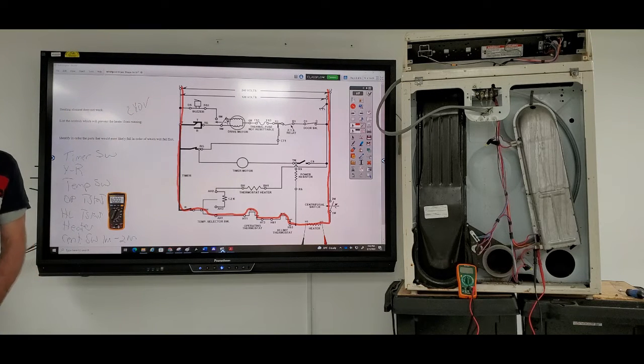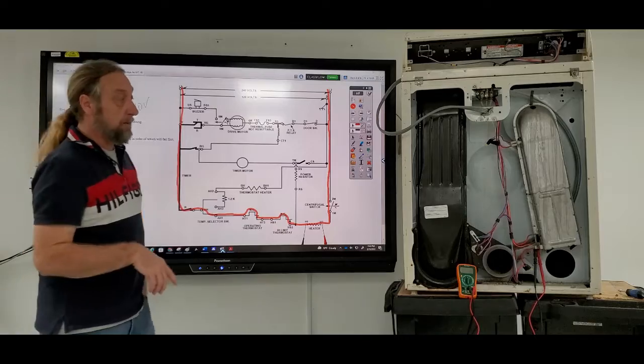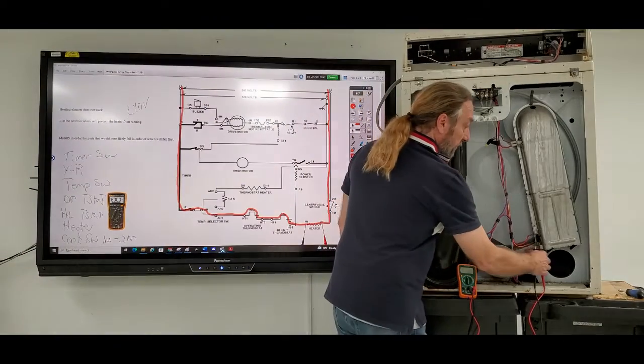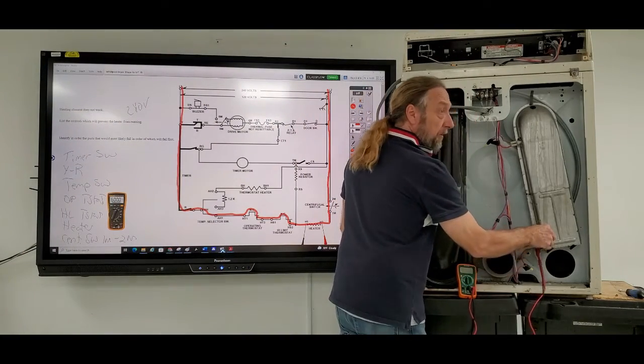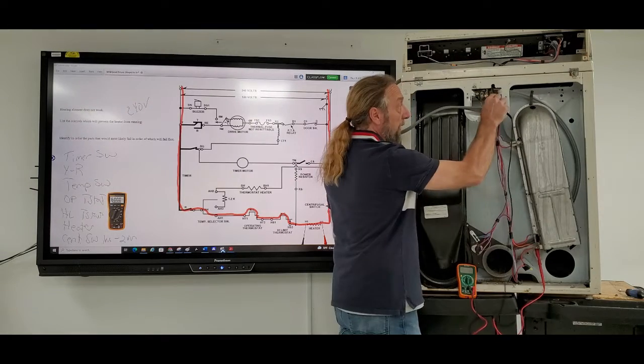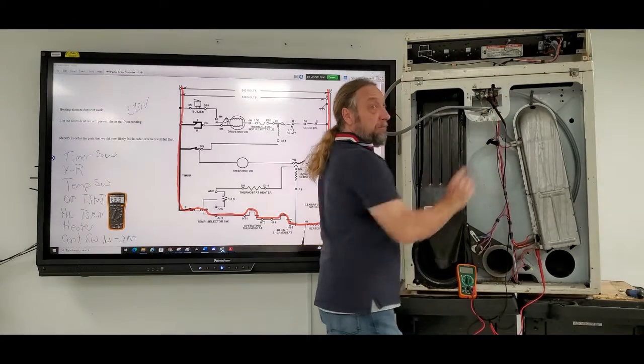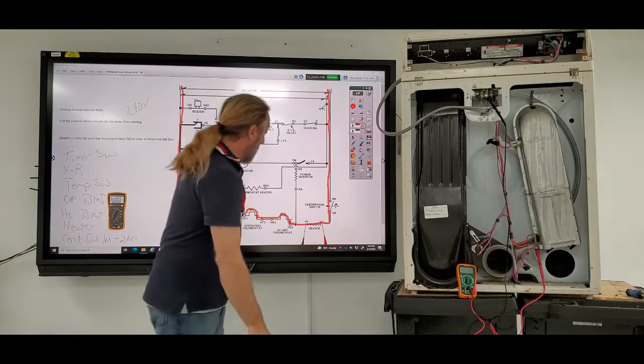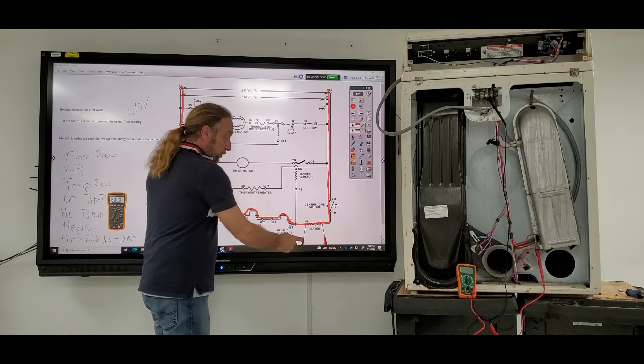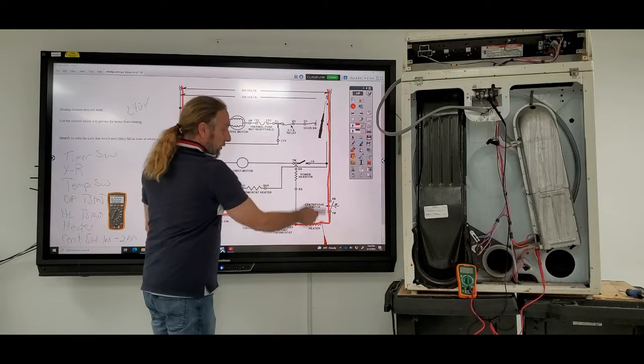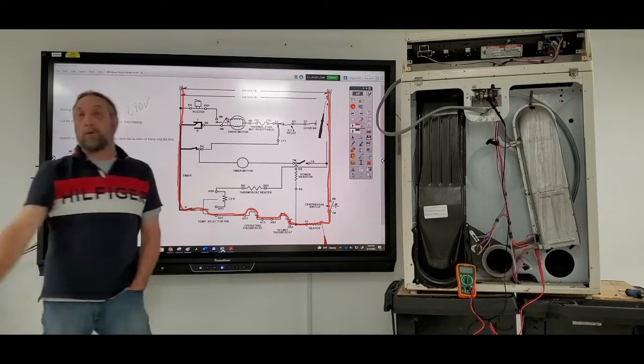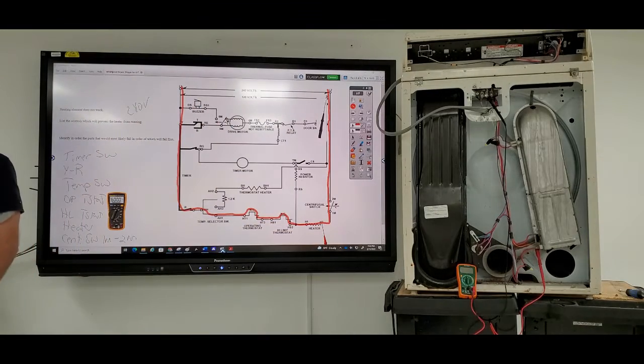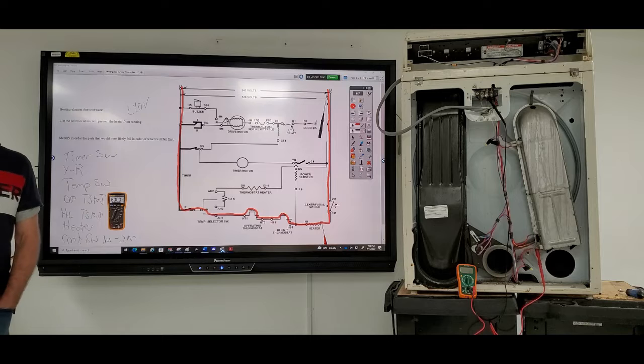Now, one thing people do which is inaccurate is they'll take this lead to ground, or to neutral, and they'll get 120 volts. They'll say, oh, I got one meter lead on H2 and the other on neutral, and I got 120, so my centrifugal switch is good because that's one side of the circuit. No. You cannot check a 240 volt circuit to ground and find the problem.